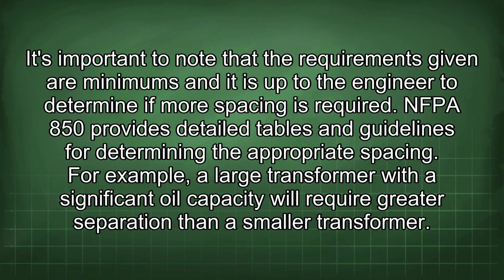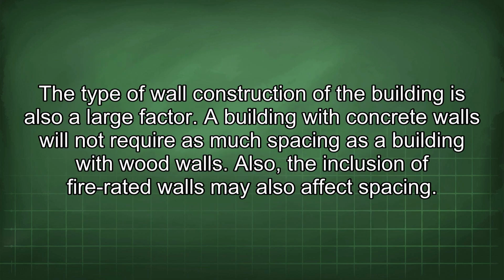For example, a large transformer with a significant oil capacity will require greater separation than a smaller transformer. The type of wall construction of the building is also a large factor. A building with concrete walls will not require as much spacing as a building with wood walls. Also, the inclusion of fire-rated walls may also affect spacing.